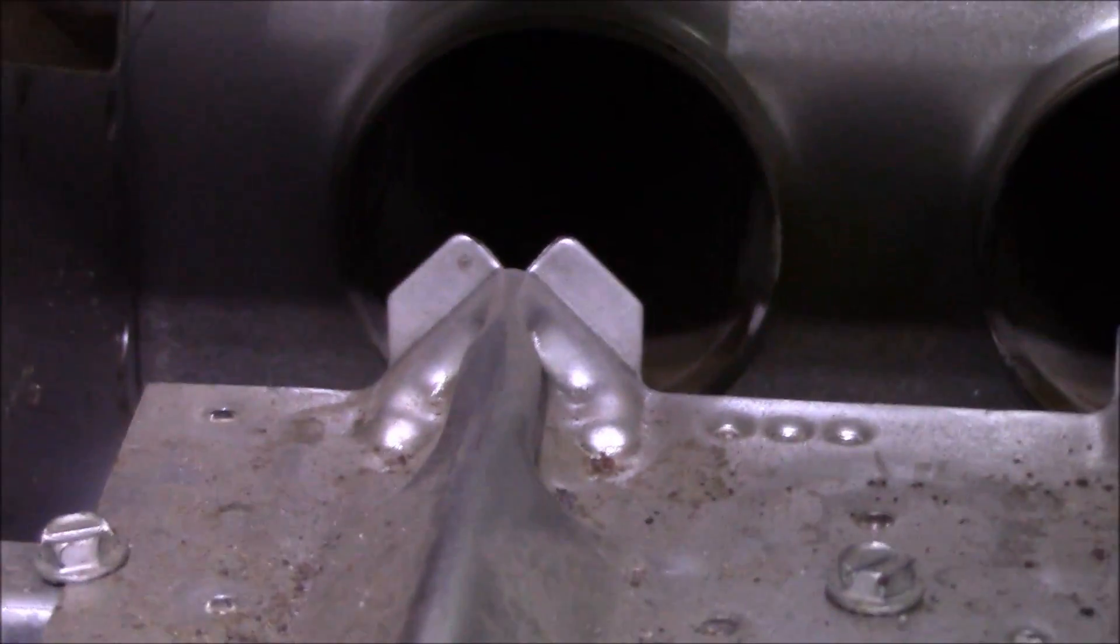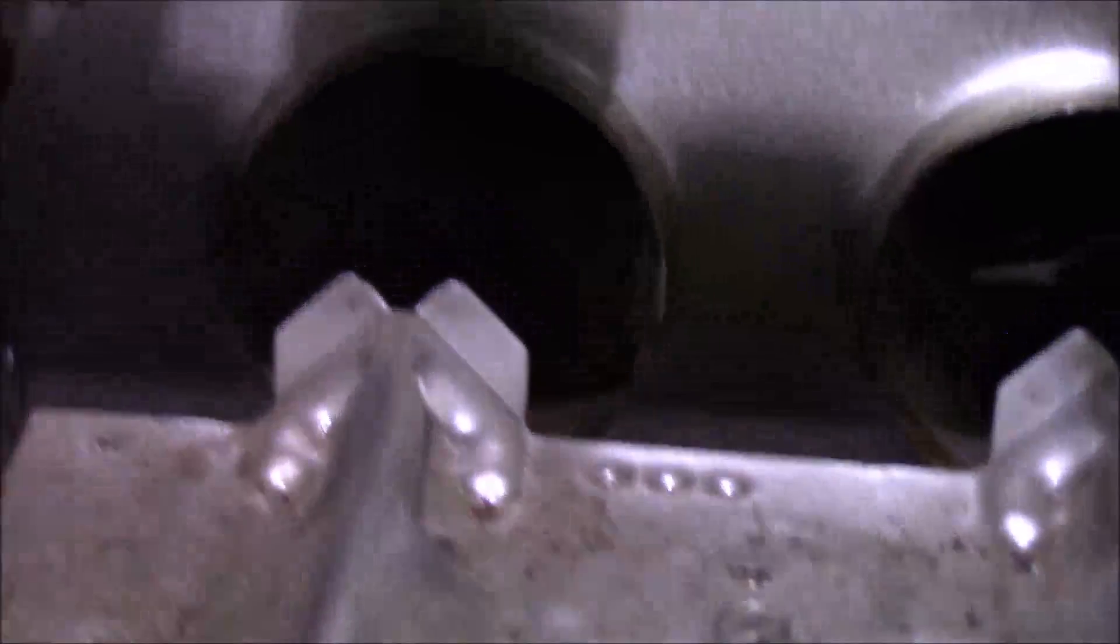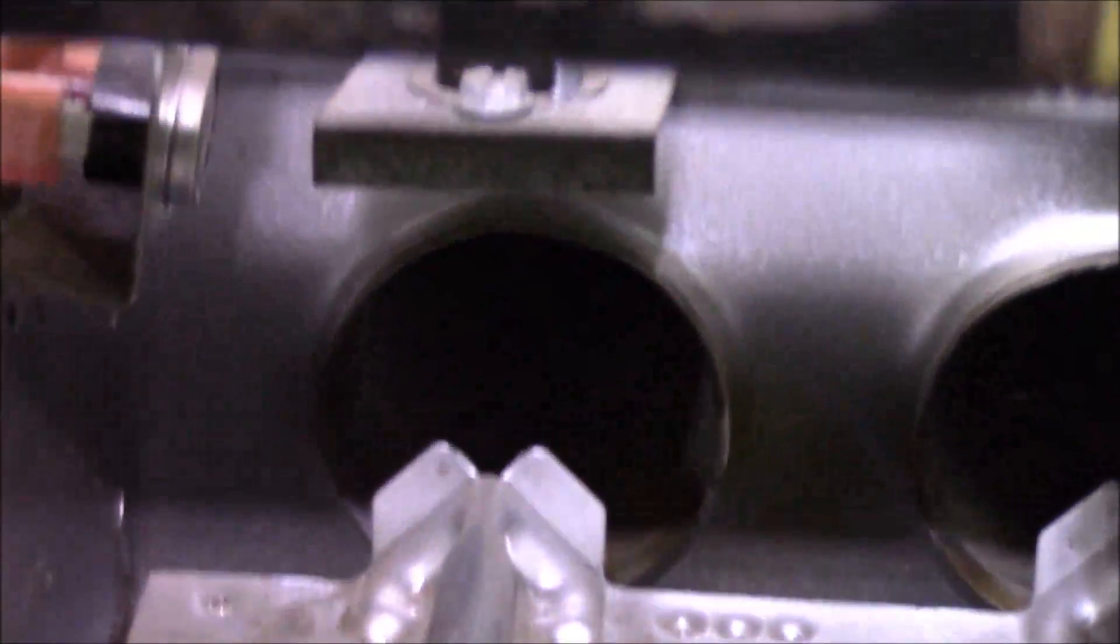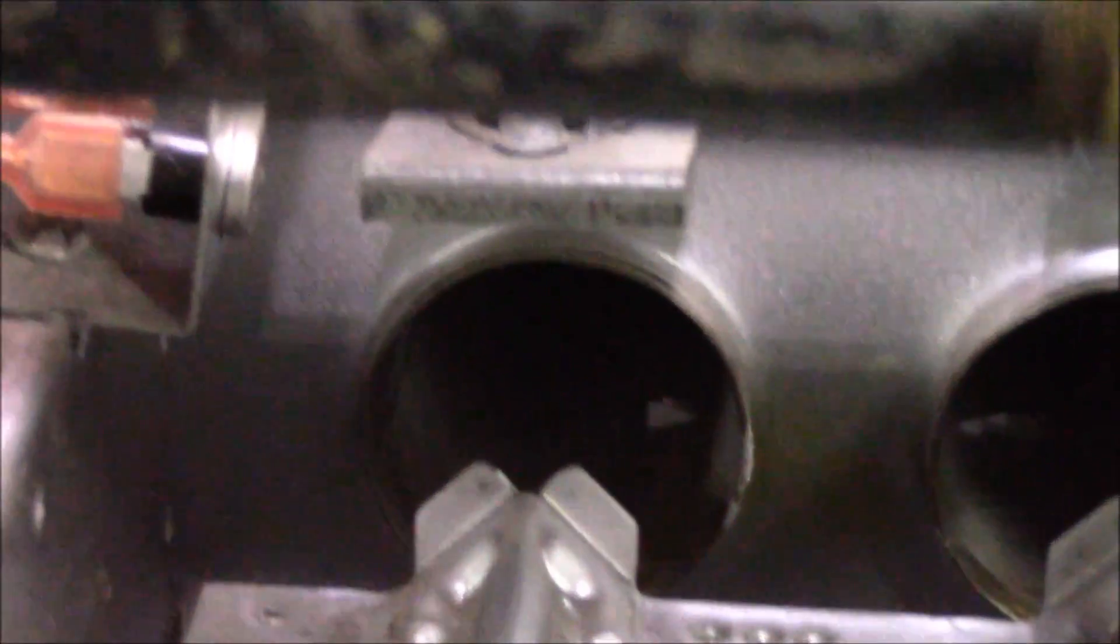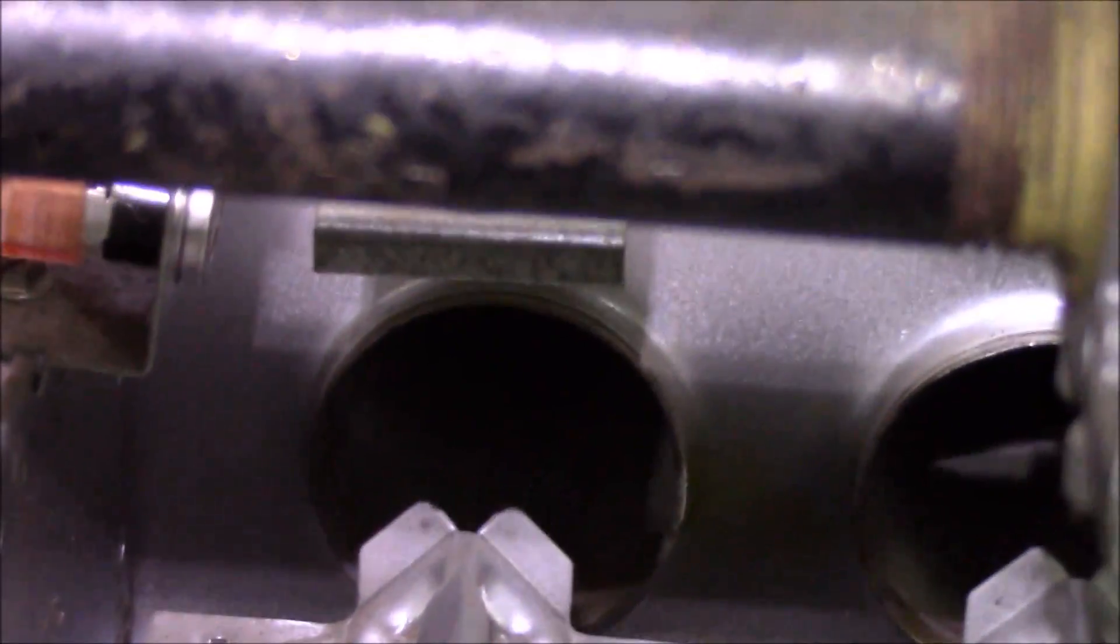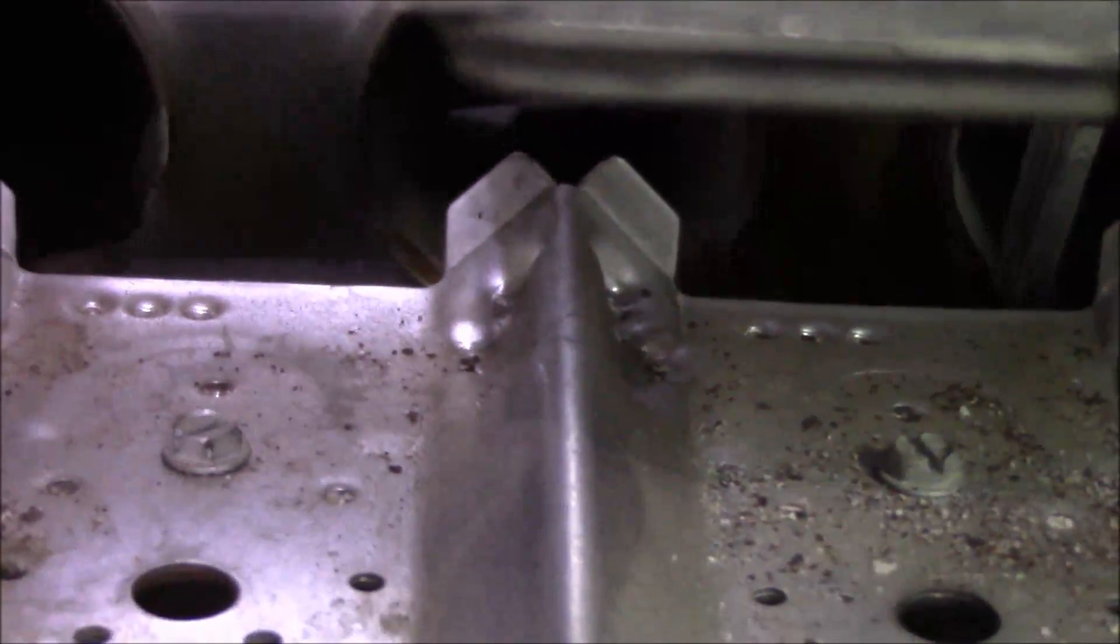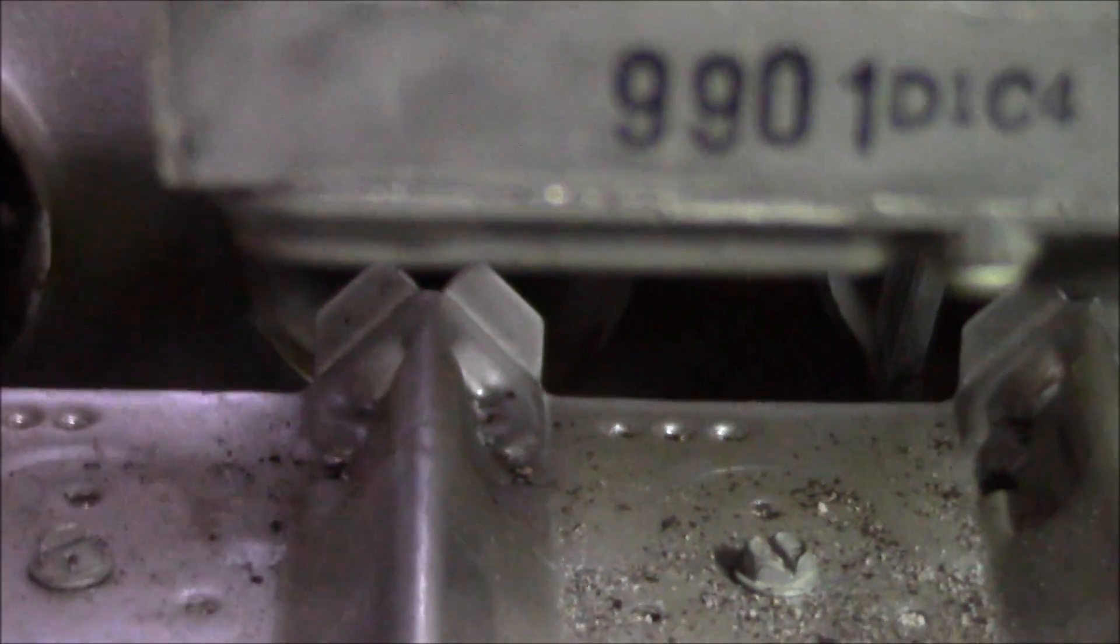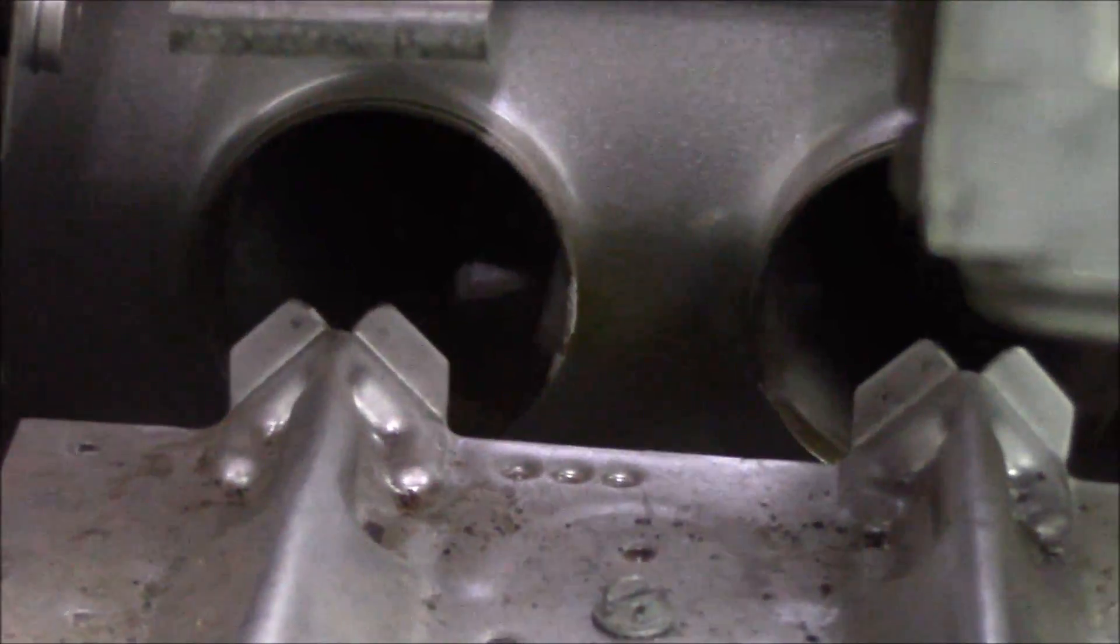Well, if you put the flame sensor and igniter together but something didn't light over here because the crossover was dirty, you're dumping natural gas in an area and at some point you could have a dangerous situation. If the flame sensor does not pick it up here because something clogged up the pathway on the crossover, it will shut off and not allow a furnace to run.